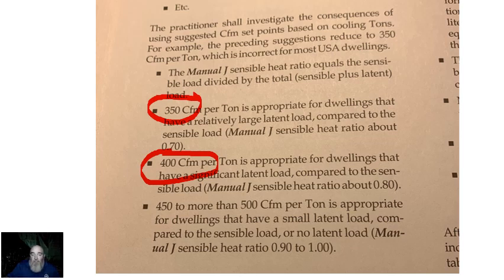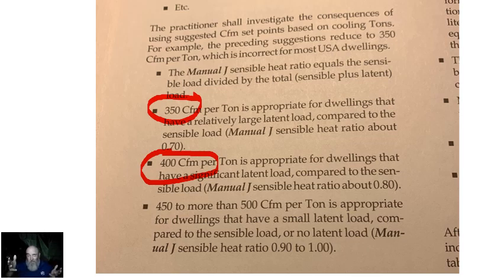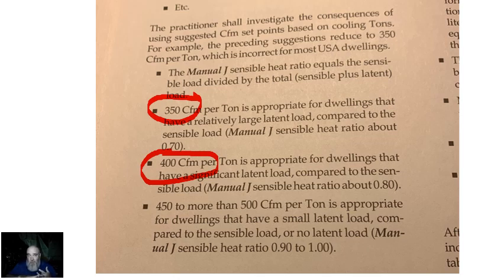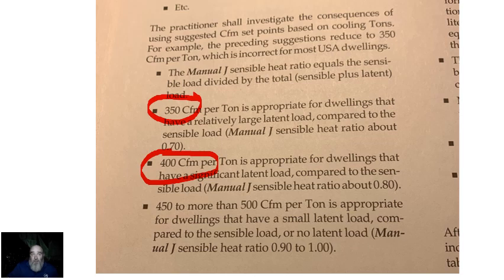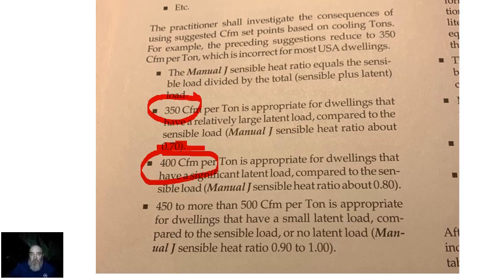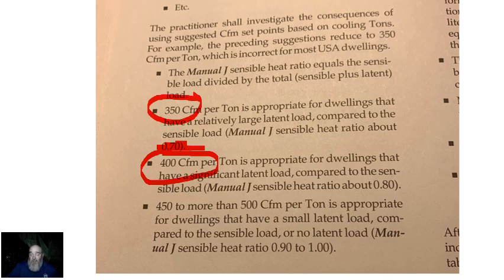This is actually an excerpt, I think, out of Manual D. I'm going to sum it up. You do a load calculation, and then you select your equipment as per Manual S. Manual S gives us guidance on what our airflow is supposed to be. Our airflow and duct design is based off of sensible BTUs. If you do a load calc and you come out with a low sensible heat ratio, something that's approaching 0.7, that would be a very wet house. Airflow in the 300 to 400 range, 350 target is advisable.